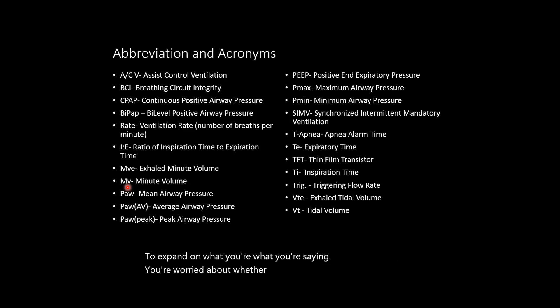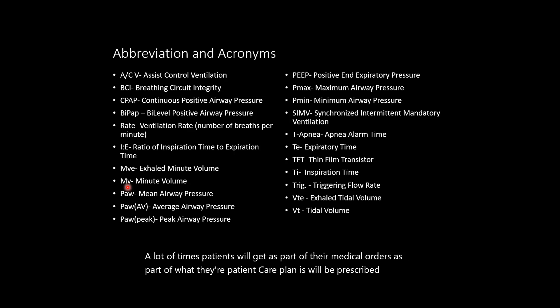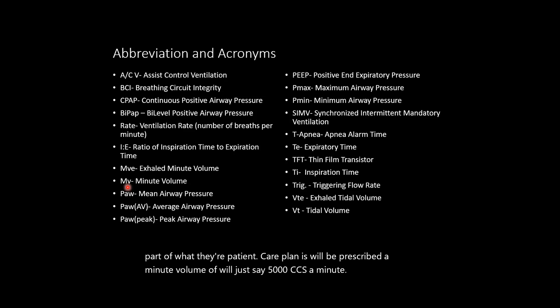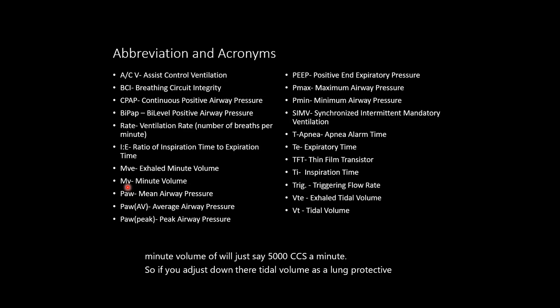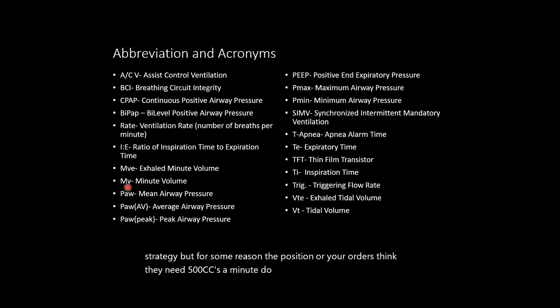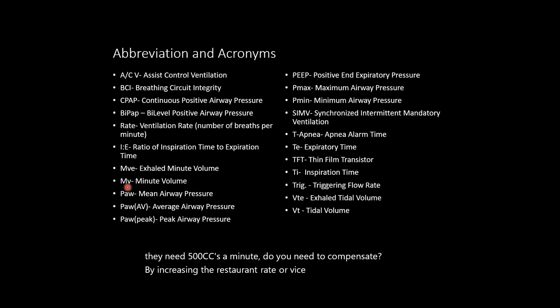A lot of times patients will get, as part of their medical orders, as part of their patient care plan, a prescribed minute volume of, we'll just say, 5,000 cc's a minute. So if you adjust down their tidal volume as a lung protective strategy, but for some reason the physician or your orders think they need 5,000 cc's a minute, then you need to compensate by increasing the respiratory rate, or vice versa. It's a balancing act. Does that make sense? So minute volume is really representative of what we anticipate their physiological needs for airflow to be. And we need to adjust the tidal volume and the respiratory rate and other parameters to meet that. Does that make sense?